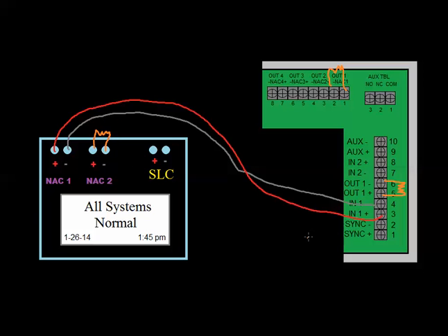Because it's really common to see the batteries fail or some trouble on the FCPS other than an actual NAC fault, which it could still be a NAC fault, but any trouble at all is going to show up as open circuit NAC 1. Whether it's batteries, ground fault, AC fail, short circuit on one of the outputs, whatever the case may be, it's going to show up as a NAC 1 trouble.